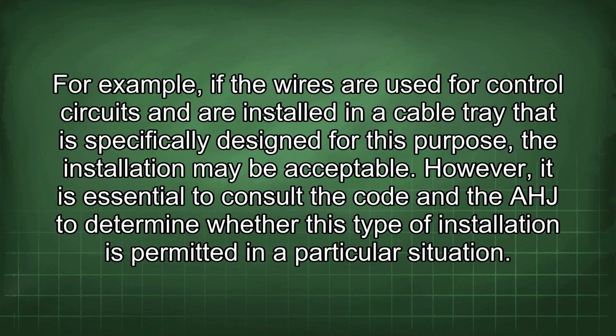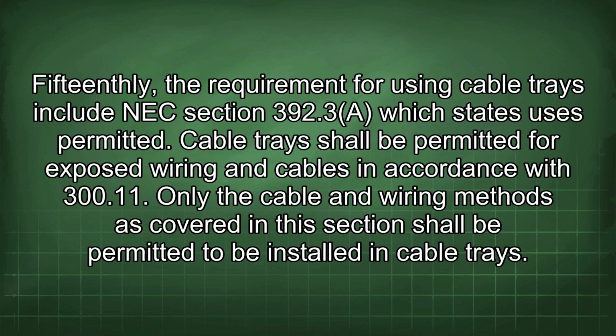For example, if the wires are used for control circuits and are installed in a cable tray that is specifically designed for this purpose, the installation may be acceptable. However, it is essential to consult the code and the AHJ to determine whether this type of installation is permitted in a particular situation. 15thly, the requirement for using cable trays include NEC section 392.3, which states use is permitted.